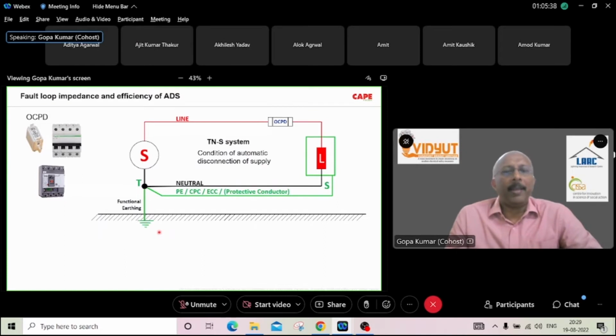this is explained again? I'm showing you a circuit. It starts with a transformer. S is for source. You have the line, meaning the live conductor, the phase, through an OCPD, through an MCB or a fuse. It goes to a load. The neutral is connected back. Body of the equipment is connected back to the neutral of the source through a separate conductor, and this is called a TN-S system. For industrial and commercial premises, we are supposed to make a TN-S system.